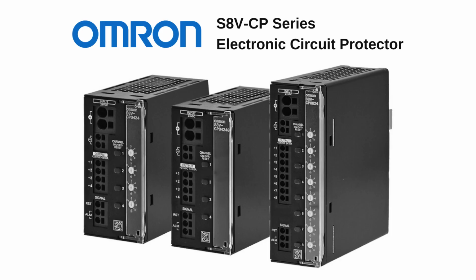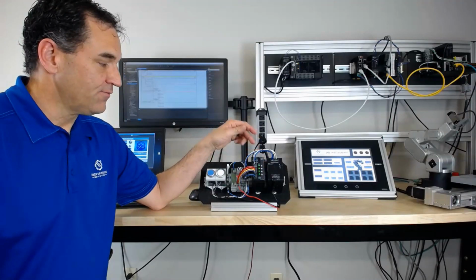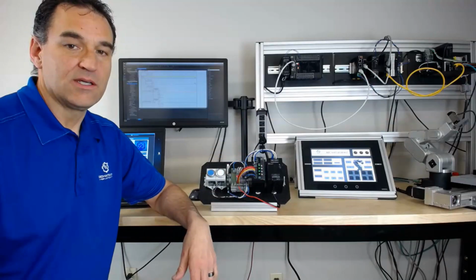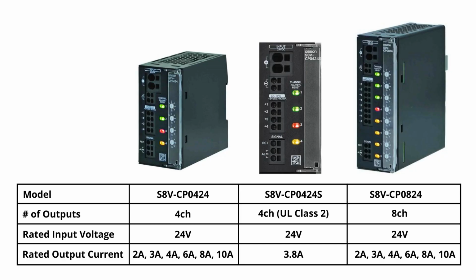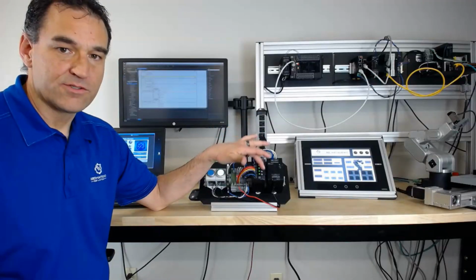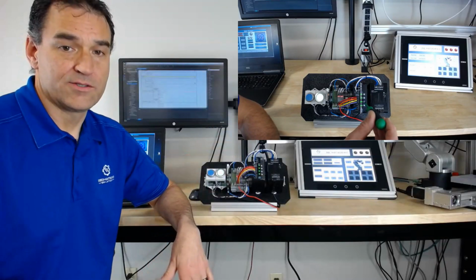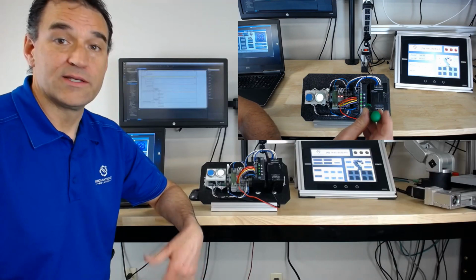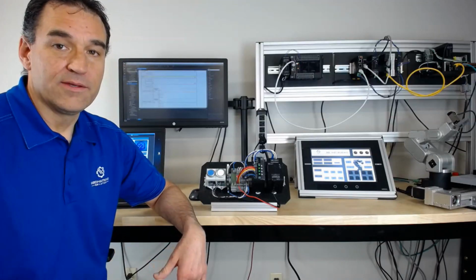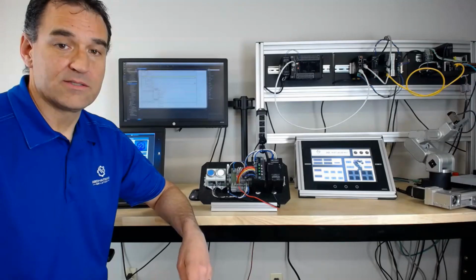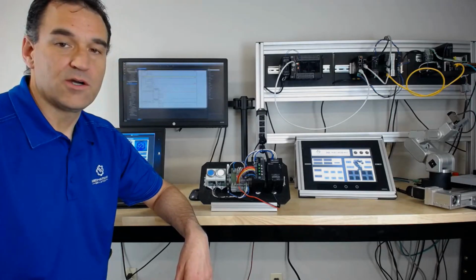Today we got the Omron S8V-CP. It's a 24-volt DC electronic circuit protector. Comes in three different varieties, a 4-channel with adjustable outputs that you see here, an 8-channel version of this, and then a 4-channel UL Class 2 version. The 4 and 8-channel versions with the adjustable outputs let you adjust between 2 and 10 amps on your output side. The UL Class 2 version is fixed at 3.8 amps on each output.